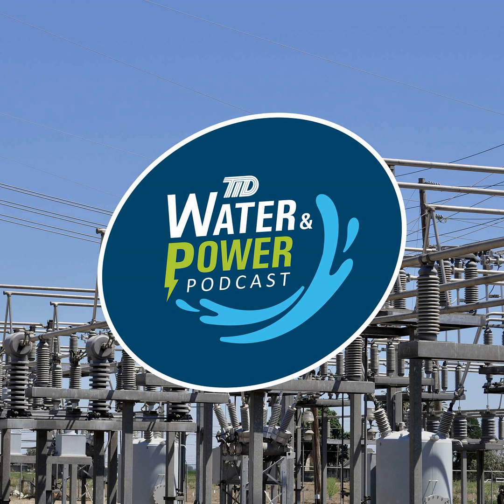So then, similar question, but the inverse: what is the district's smallest substation? The smallest substation is our college substation, and it's really more of a tap substation. It's unique in that it's located off of a transmission line—we basically connect into it. We have a transformer and load, but not a lot of protection available from that facility; protection on that line ends up happening at two other substations, based on how it's connected to our system.